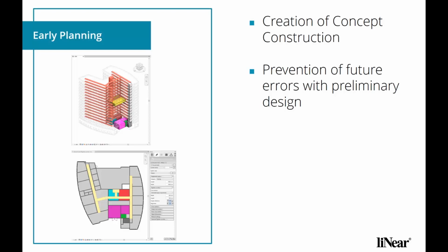With the tools you can determine realistic requirements for the equipment rooms and coordinate this with other parties involved, for example the architect, in the very early design phases. This enables active conflict avoidance instead of costly changes having to be made in the course of conflict resolution in the later design processes. The space required by the equipment rooms of the individual trades can be determined quickly and easily in accordance with the rules of VDI 2050 with just a few specifications or specified based on experience.